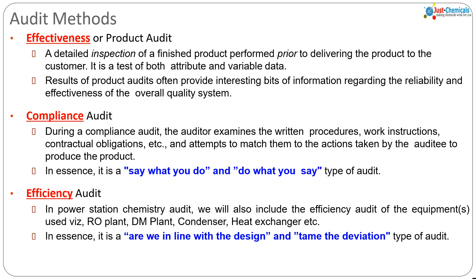It is important to note that effectiveness relates to the external environment or the customer — for example, DM water quality is the effect delivered to the customer. Efficiency is internal, assessing performance and opportunities for improvement. For example, if the output between regenerations of your ion exchanger is not up to the mark or not matching with the inlet water quality, that is a subject for an efficiency audit.